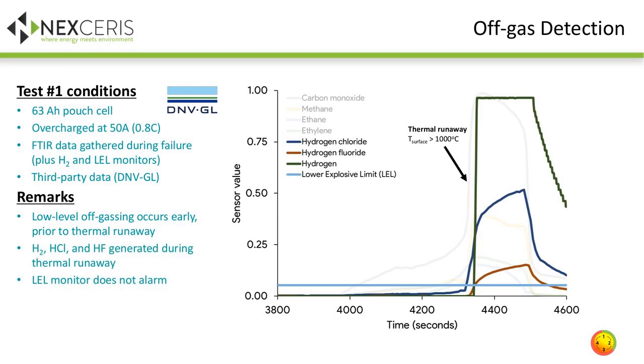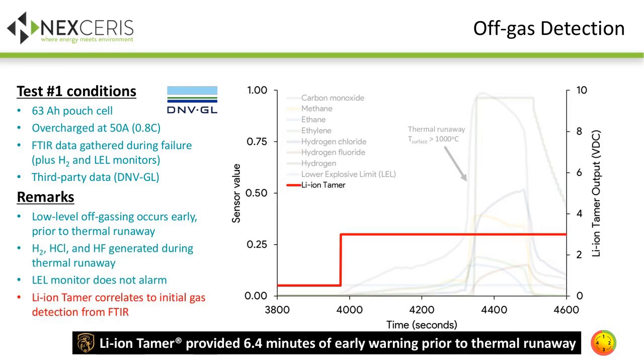If you overlay some of the other gases, I won't go into detail on those, but the final overlay here is what can be accomplished with off-gas detection. And this technology that we work on, which is called Li-ion Tamer, was able to provide 6.4 minutes of early warning prior to thermal runaway. So it gives you an improved situational awareness of a fault that is beginning to occur within your battery system and provides some time prior to that.